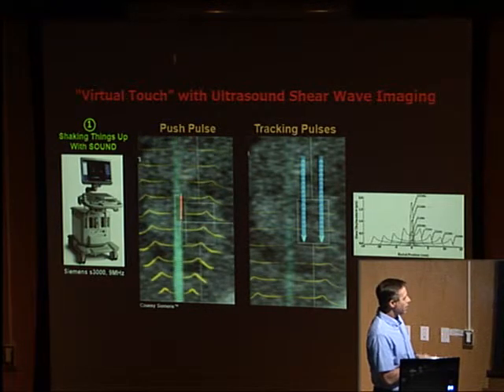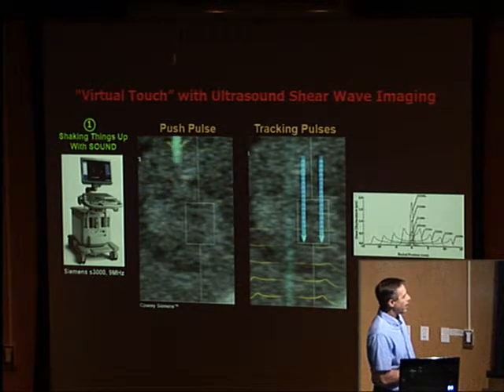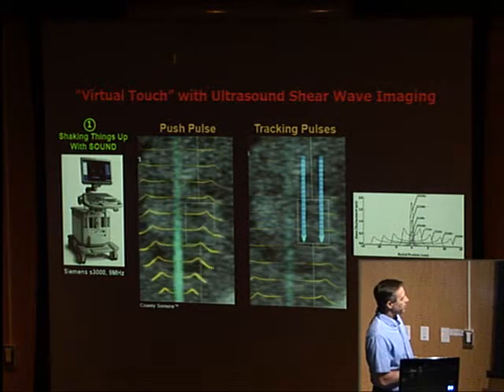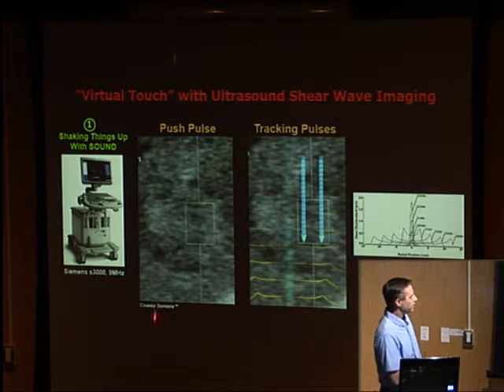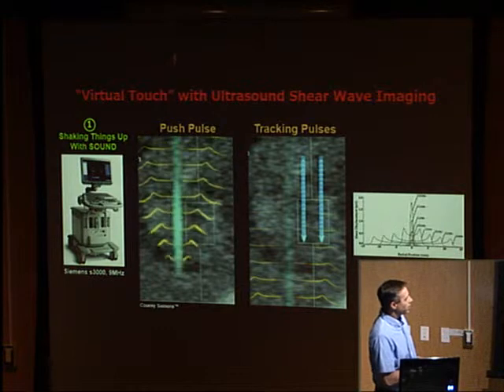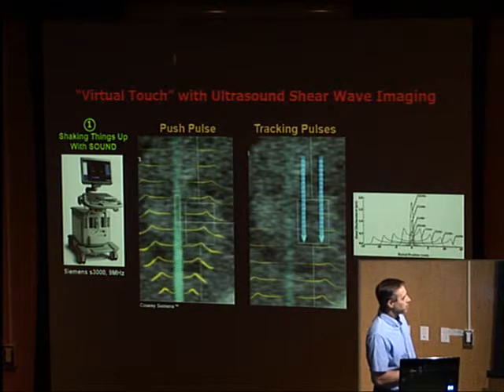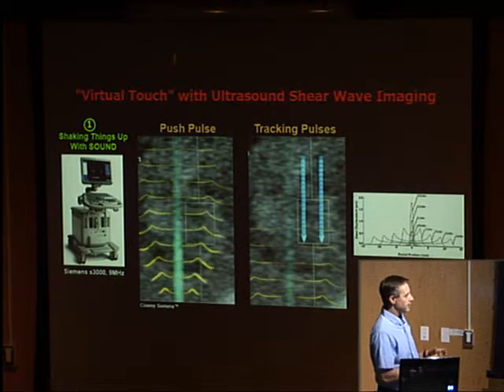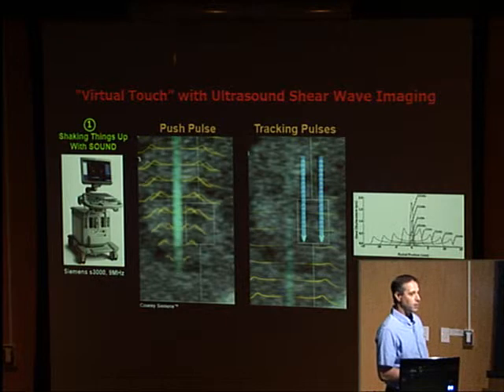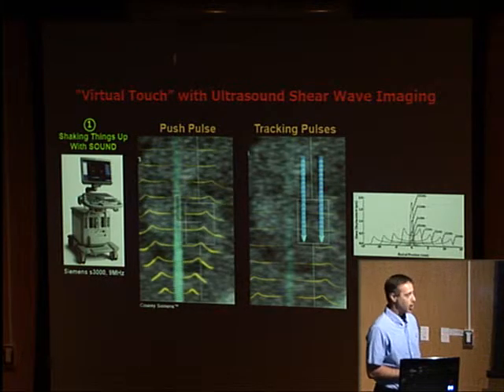You hit it with a long push pulse with the ultrasound, and this creates shear waves that propagate perpendicular to this longitudinal beam. And then right after you push, you then have these tracking pulses that allow you to track the displacement and speed of these waves as they propagate. And it turns out the speed of that wave is directly related to the mechanical and elastic properties of the tissue.